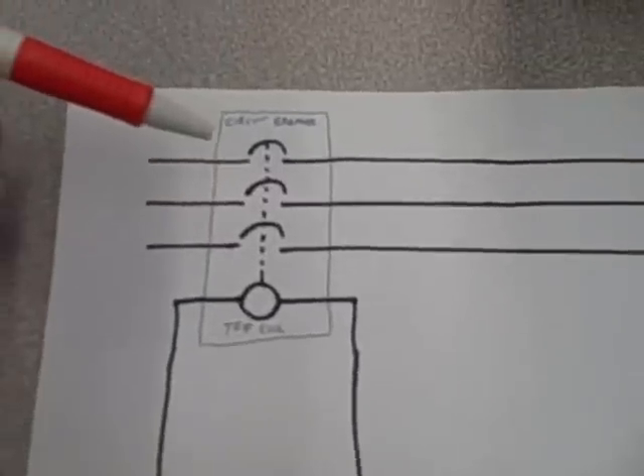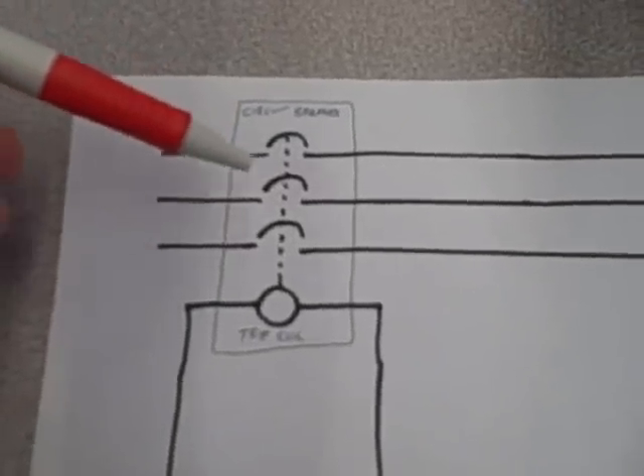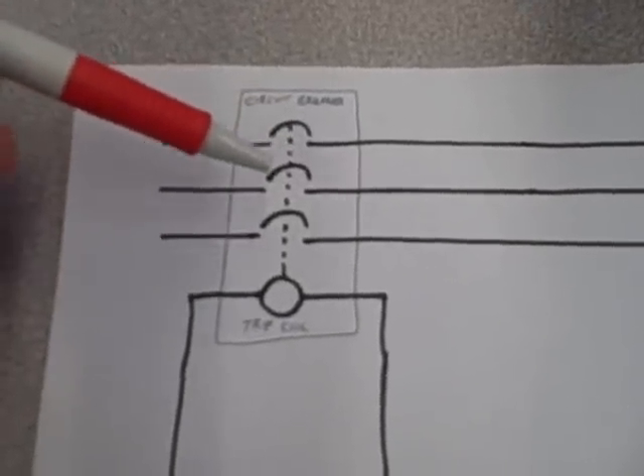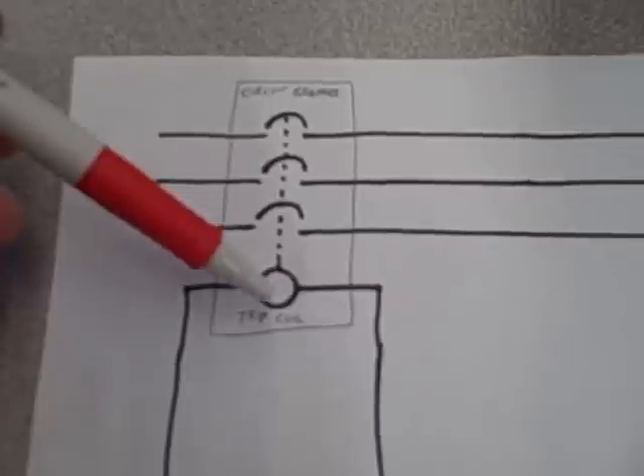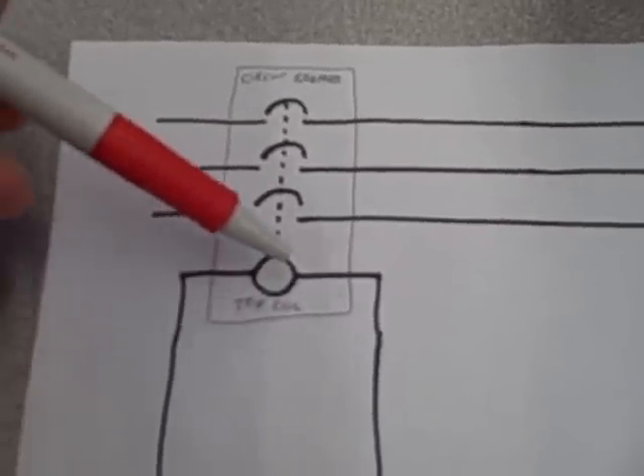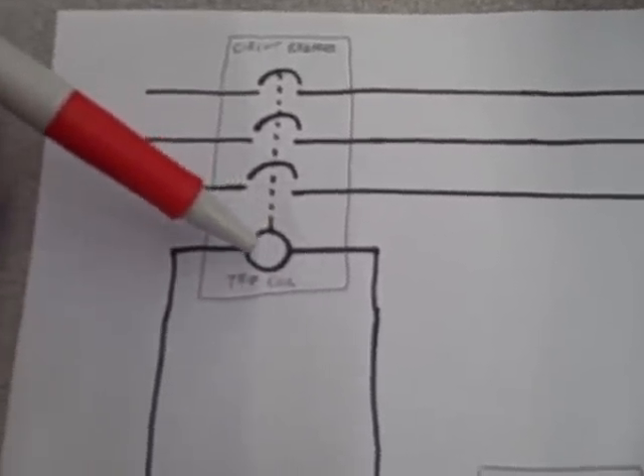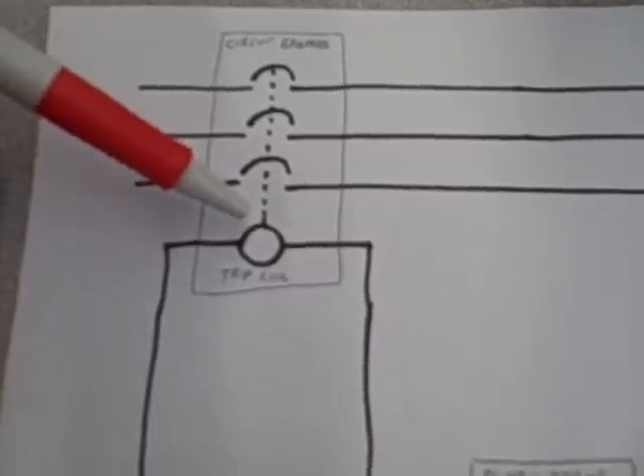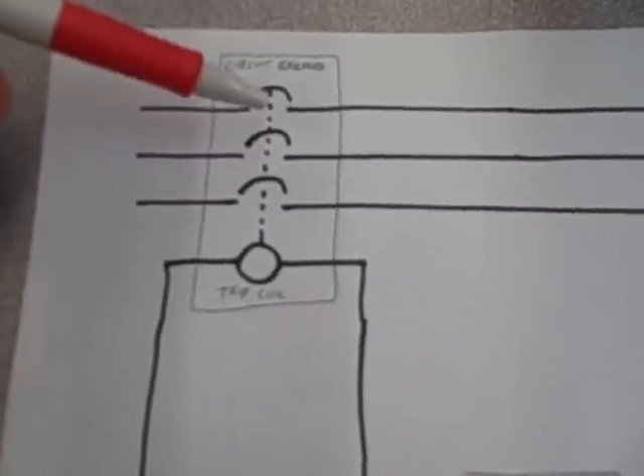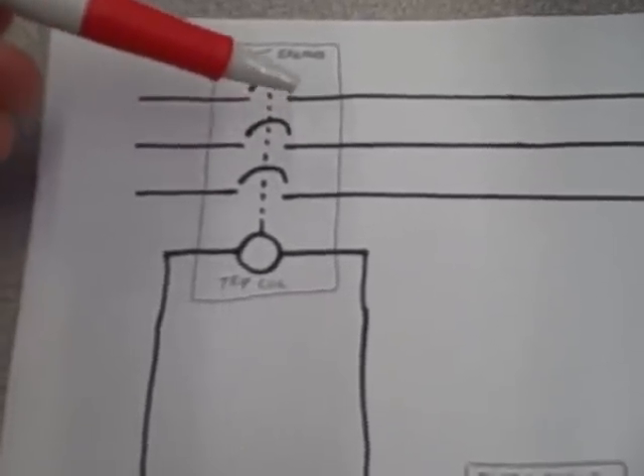The circuit breaker is not like the circuit breaker in your home. It's not a thermally operated device. It actually has to be told to trip by a trip coil. If we energize the solenoid trip coil here, what happens is it unlatches a mechanism and spring tension will open the breaker contacts and interrupt current at the circuit.